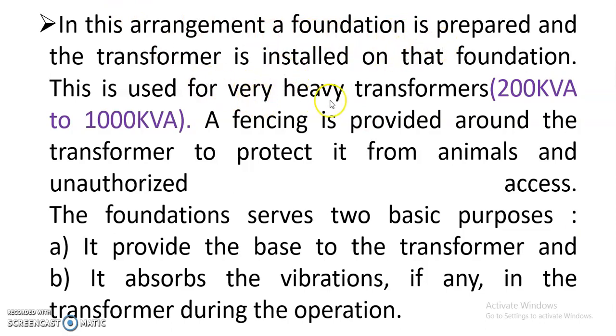This is used for very heavy transformers. It can be rated from 200 kVA to 1000 kVA. Then the fencing is provided around the transformer to protect it from animals and unauthorized access.